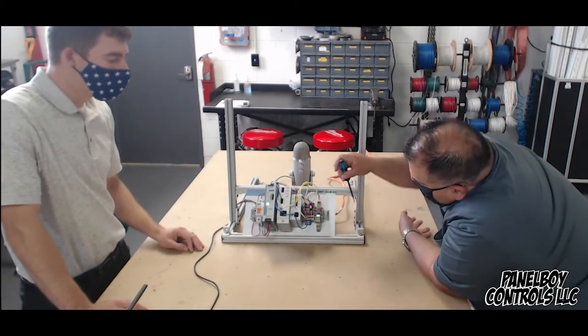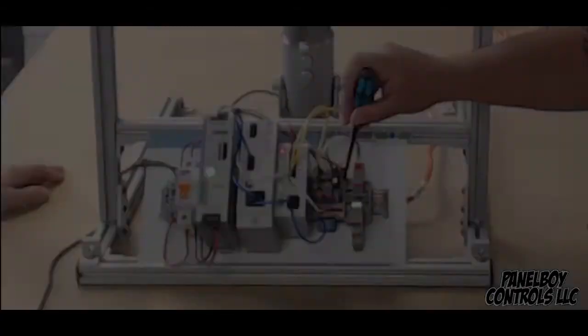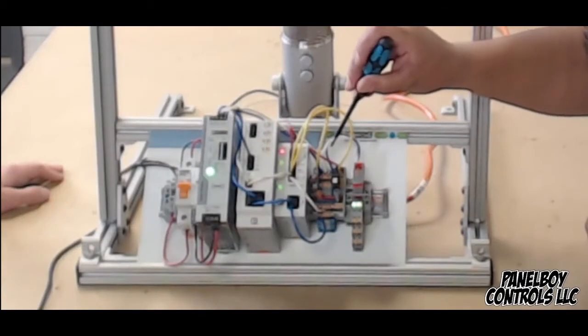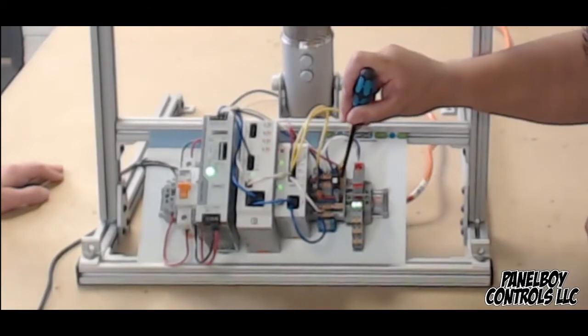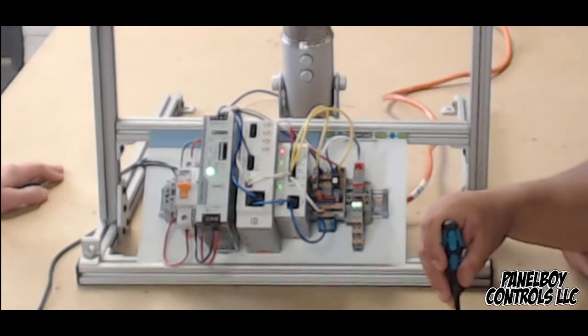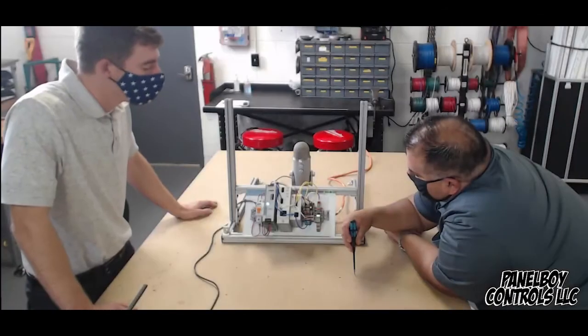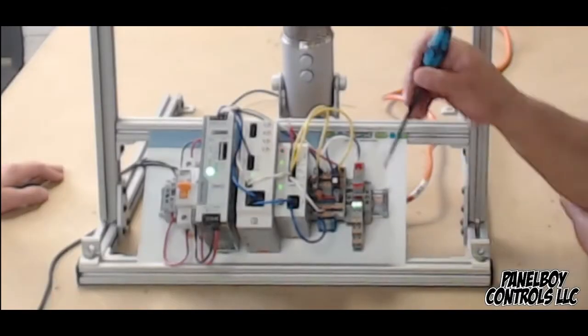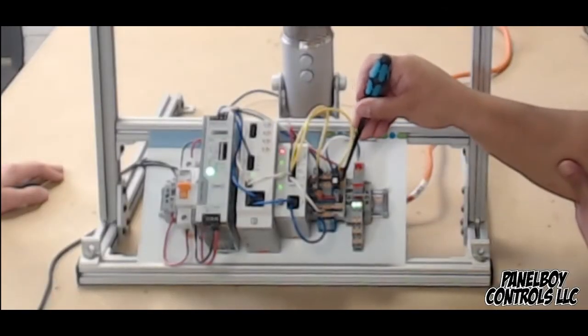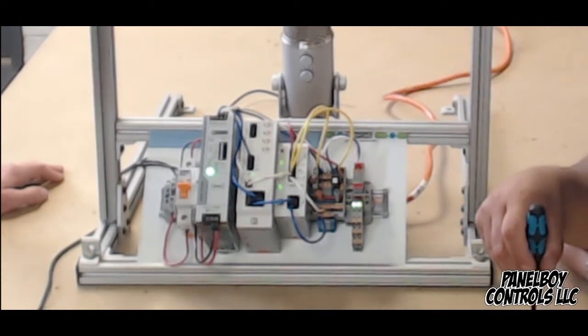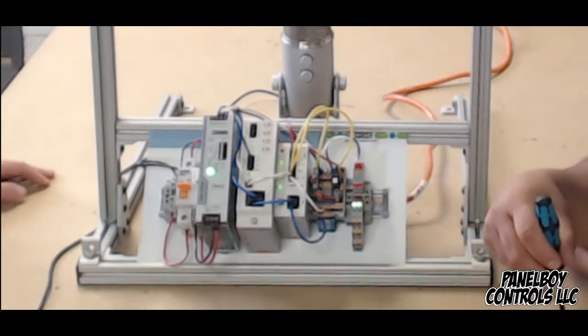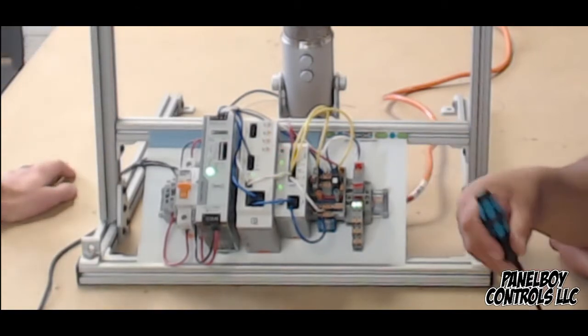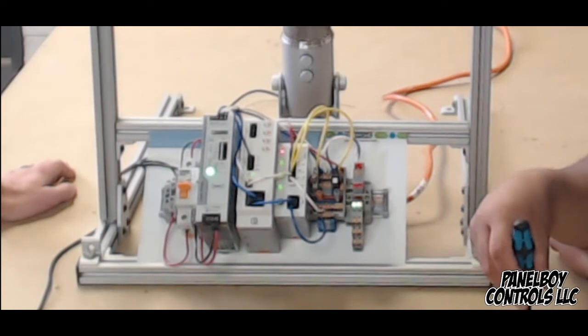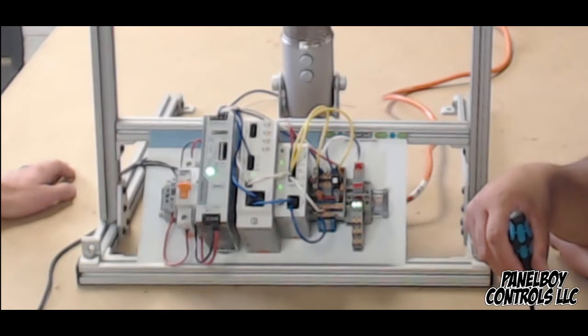Any questions so far? Could I trip that again? Yeah, if I trip it, then if I clear it, I'm just trying to see if the filter's still shorted or not. I was just checking to see if it will detect that the short still. The only way I think you'd be able to recognize that is if you try to reset it like I did the first time and it just stays tripped.